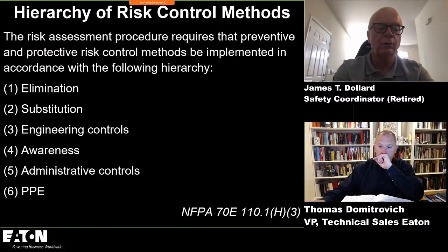Instead of installing 277 volt control circuits, let's install 24 volts. Yep. Engineering controls can be applied at almost any time, but they lend themselves well to design. We could have an energy reduction maintenance switch. We could guard. We could blanket. Awareness is labeling. Administrative controls is training and other things. And the last resort is PPE.